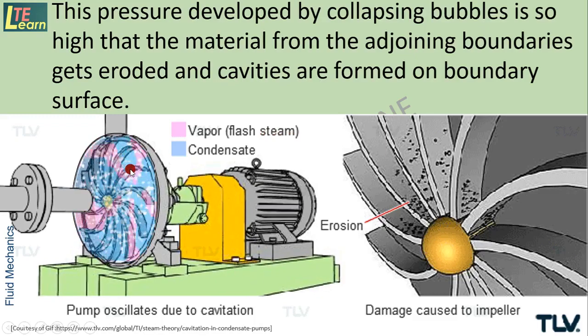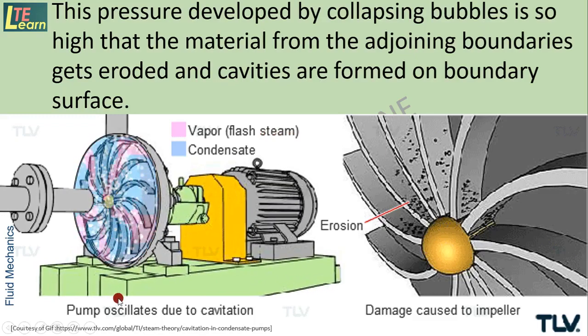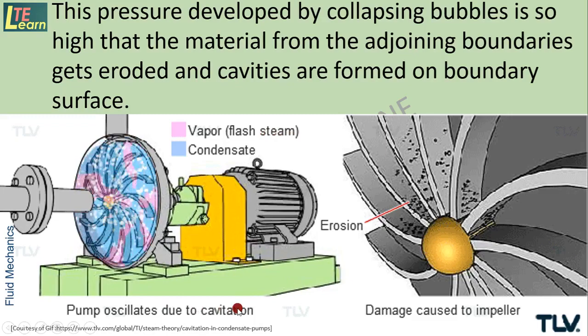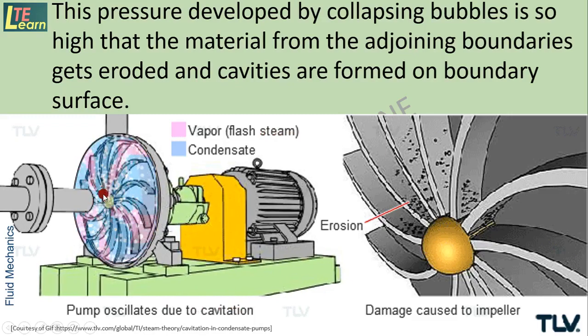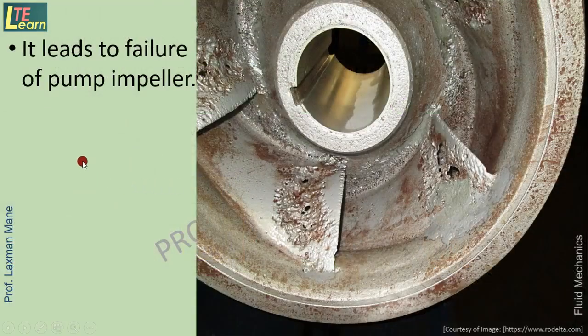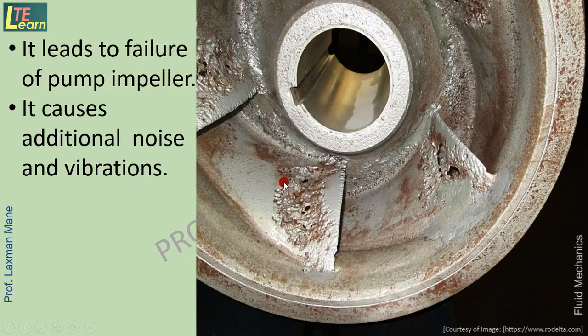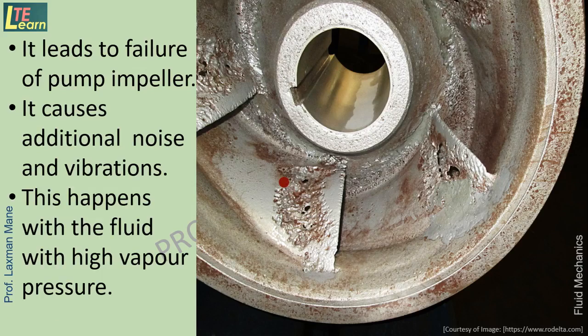When cavitation is formed, the pump oscillates due to cavitation. So it is an indication of cavitation. It leads to failure of the pump impeller. Here we see on this surface erosion and pitting action. It causes additional noise and vibrations while the pump is working. This happens with a fluid with high vapor pressure, for example petrol.